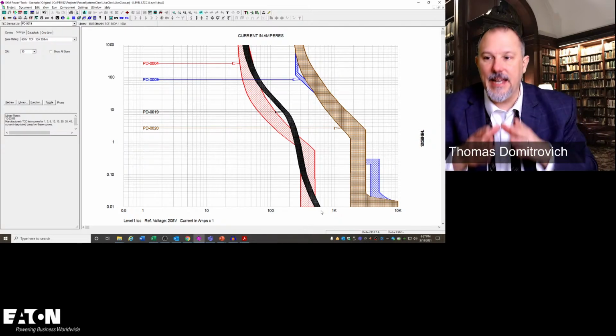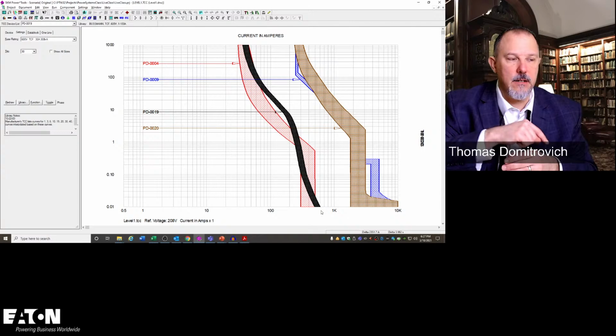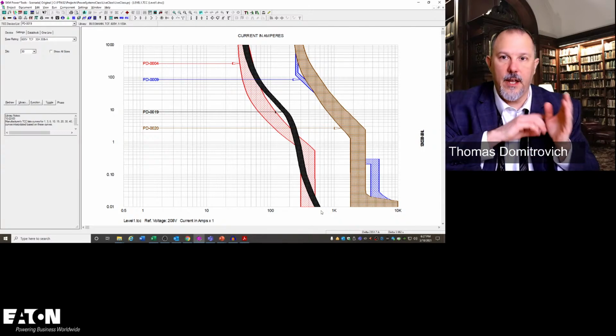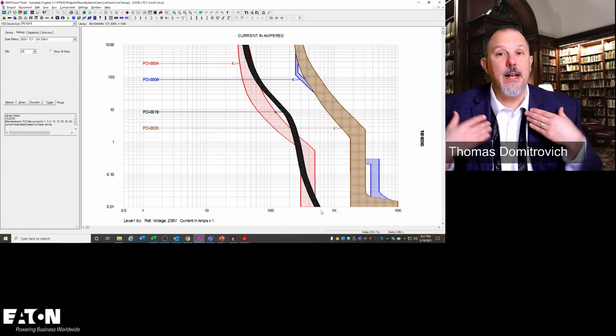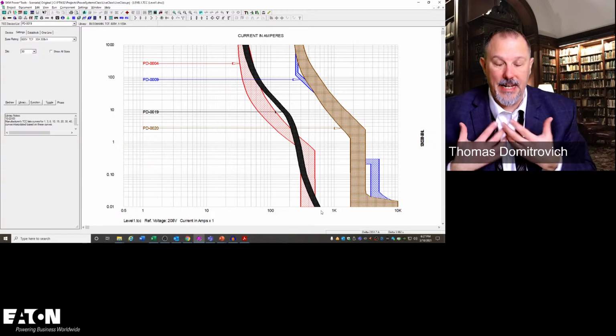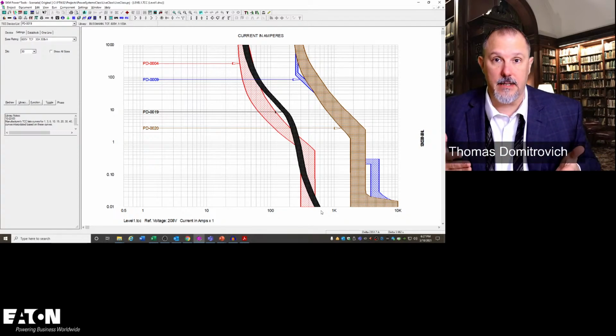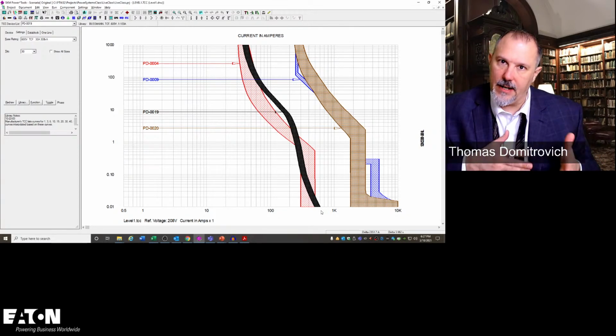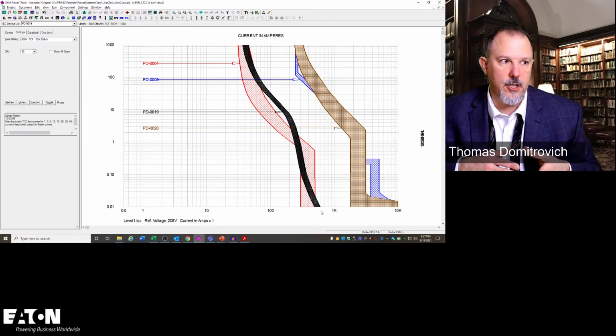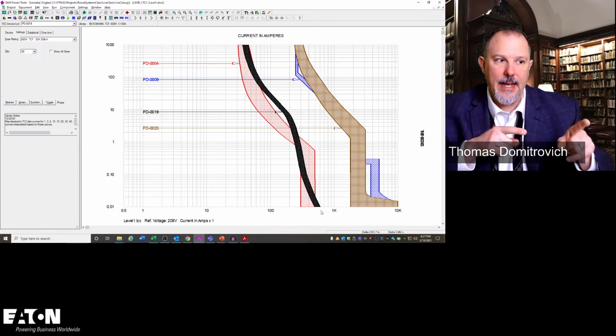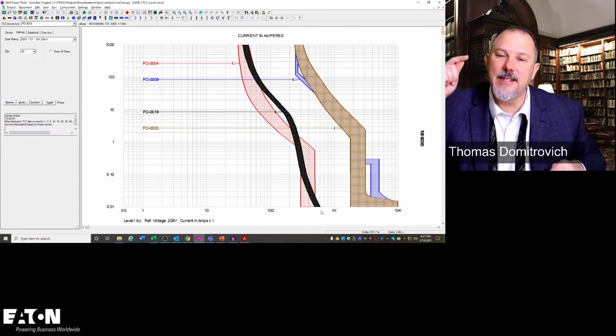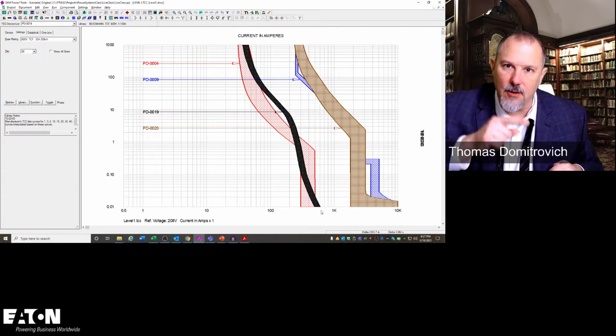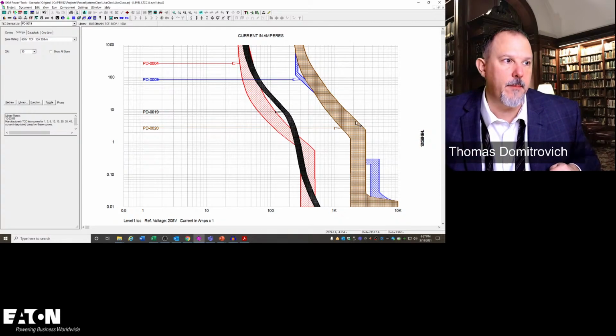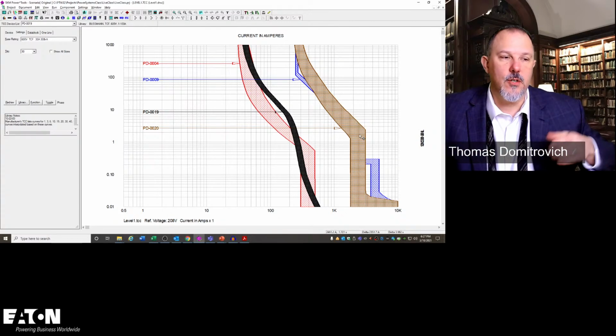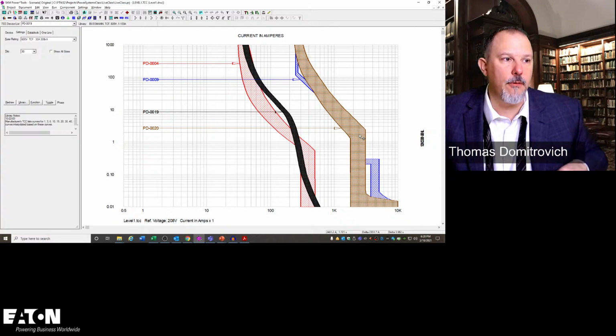So in some cases, replacing the downstream device with a current limiting type of fuse, in our case, from an Eaton perspective, we've tested these things together. So we have a little bit of an advantage over others in the industry. But I can selectively coordinate up to 65,000 amps, which is the interrupting rating of that upstream circuit breaker. So the fuse can get you out of issues.